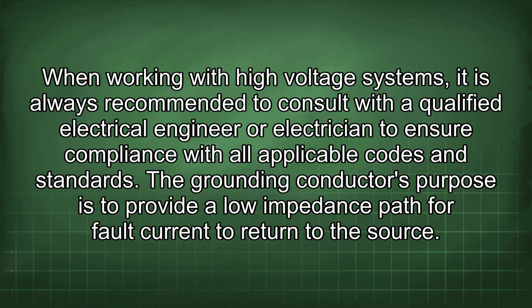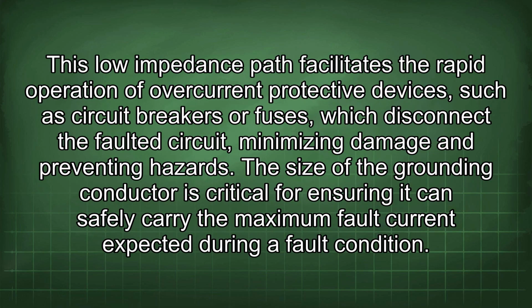When working with high-voltage systems, it is always recommended to consult with a qualified electrical engineer or electrician to ensure compliance with all applicable codes and standards. The grounding conductor's purpose is to provide a low-impedance path for fault current to return to the source. This low-impedance path facilitates the rapid operation of overcurrent protective devices, such as circuit breakers or fuses, which disconnect the faulted circuit, minimizing damage and preventing hazards.